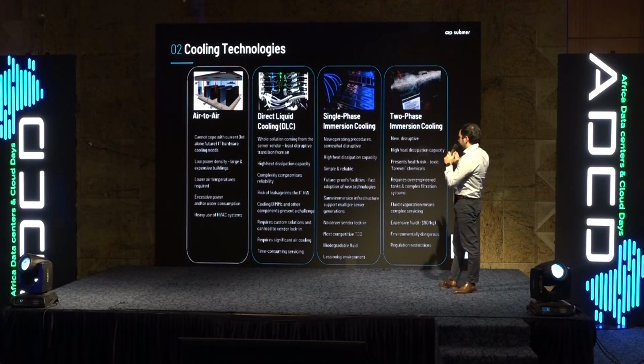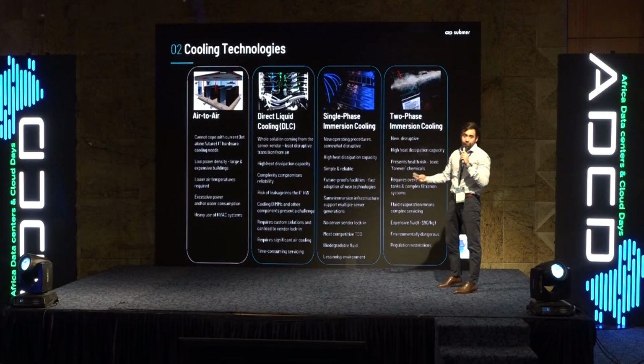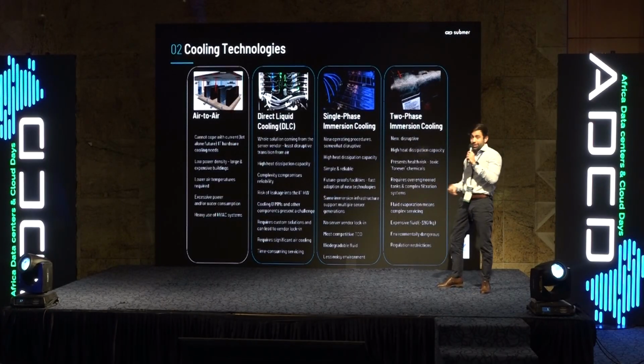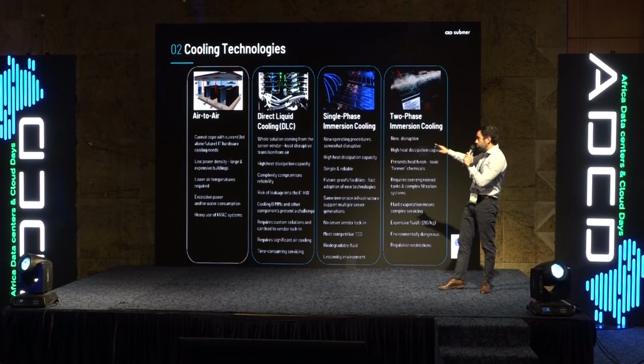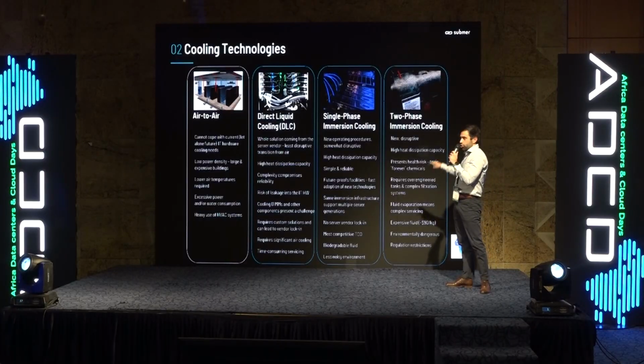In liquid cooling, there are three main technologies: DLC, direct liquid cooling or direct to chip; single phase immersion cooling, which is what we do at Submer; and two-phase immersion cooling.